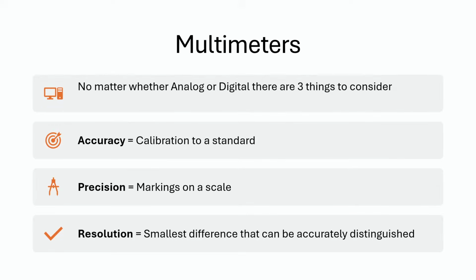The accuracy of the meter has to do with whether the meter is calibrated to a standard, a known good value. How precise are the measurements you're making? It has to do with the markings on a scale or the number of digits in a digital meter. The resolution is the smallest difference that can be accurately distinguished.